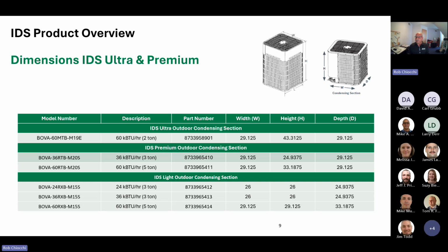There is very few physical changes between the new R454B platform heat pumps and the existing R410A platform heat pumps. They did make some minor enhancements, though, that I think dealers are going to like. One is they have recalculated the amperage requirements for the 5-ton unit. So in the past, the 20 SEER 5-ton unit on the rating plate required a 60 amp breaker. They have now lowered that rating to 45. So that should make, in some municipalities, a little easier to get away with a lower outdoor high voltage circuit.